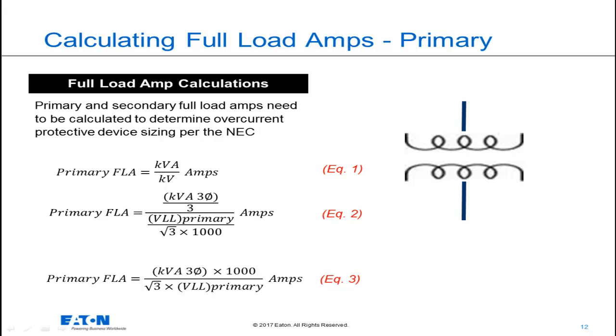Here we're going to focus on the numerator first. So we have to get to the single phase kVA, and we have a three phase transformer. So to get there, we have to divide the three phase kVA by 3, and that gets us a single phase kVA.